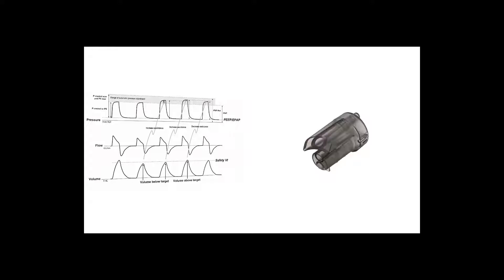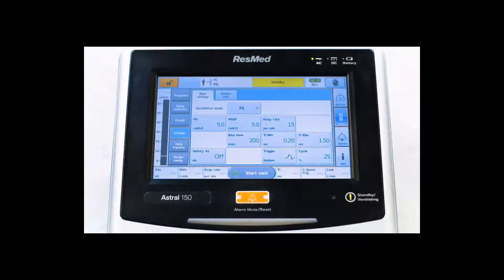Prior to configuring Safety Tidal Volume, you will need to select a single limb leak circuit adapter. Perform the Setup Assistant ensuring there are no interfaces, like masks, in place at any time during this process.